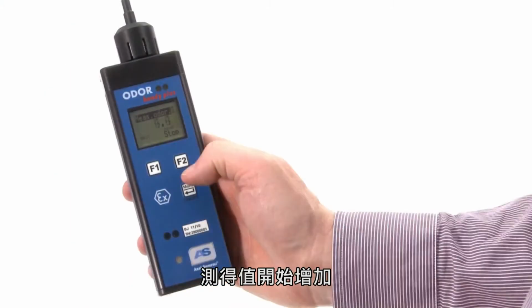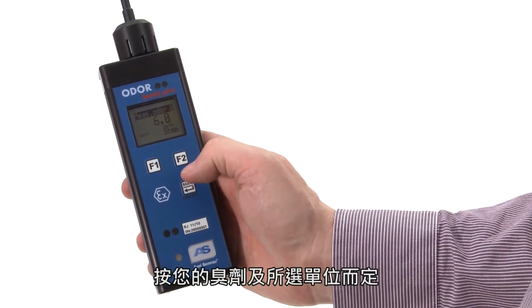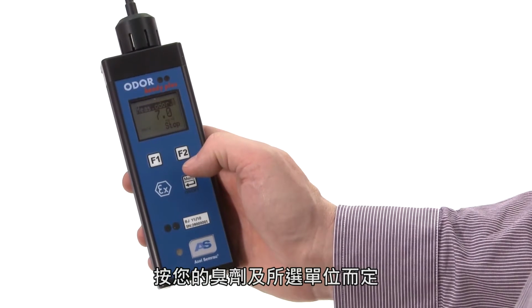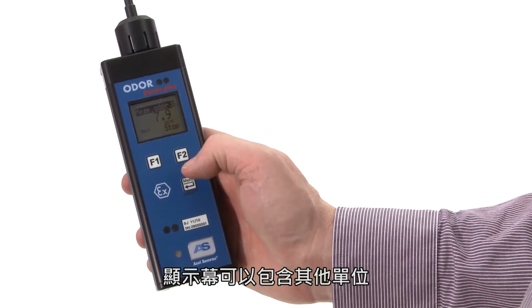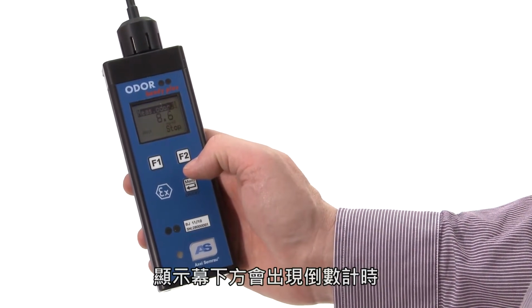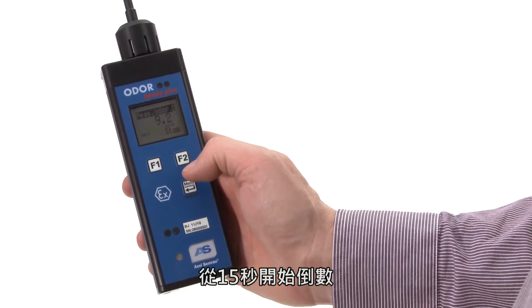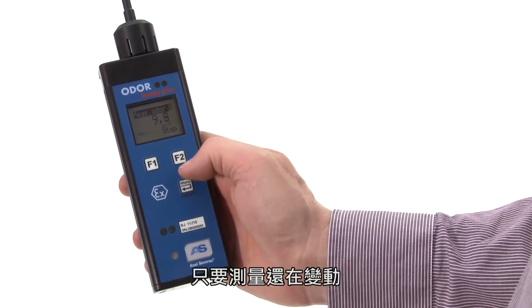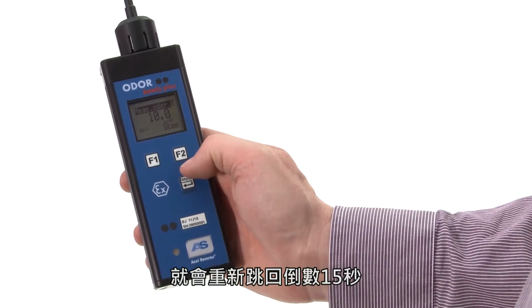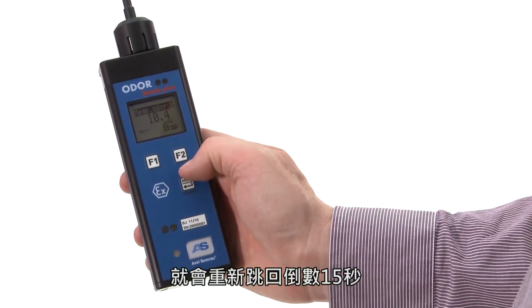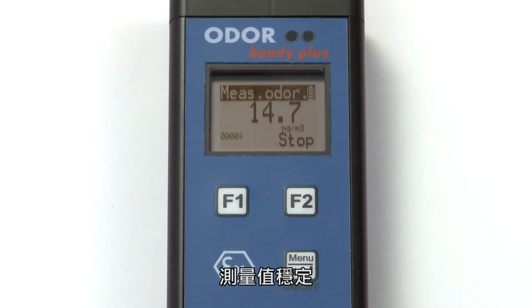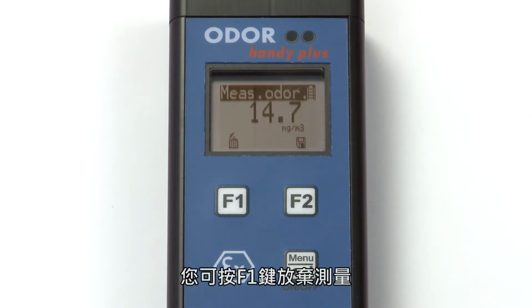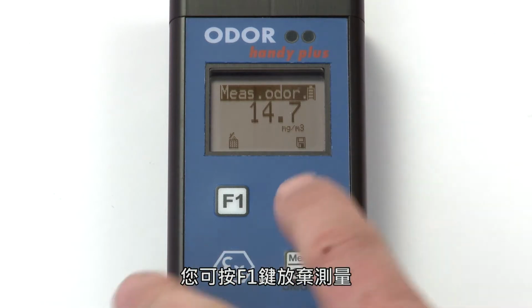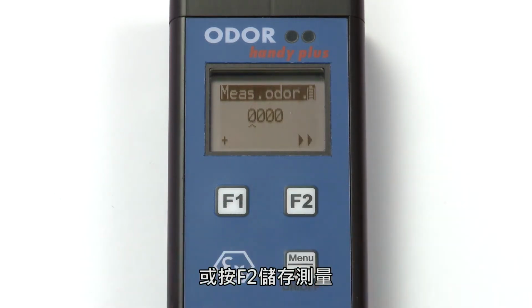You see the measured value advance. Depending on your odorant and the selected units, the display can contain other units. In the lower left half, you see a countdown. This will be counted down from 15 seconds. As long as the measurement is still changing, the countdown will continue to jump back up to 15 seconds. When the measurement is stable and the countdown reaches 0, the measurement is finished. Then you can either discard the measurement by pressing F1 or save the measurement by pressing F2.